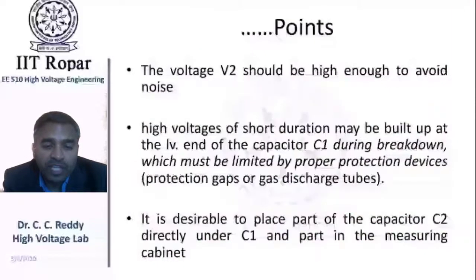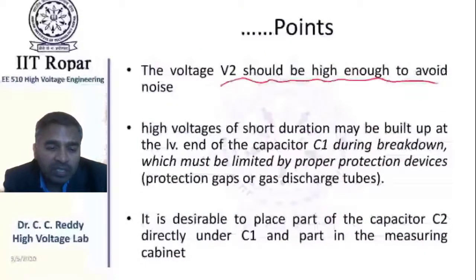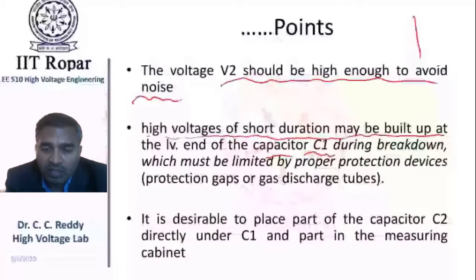And the voltage V2 should be high enough to avoid noise, because if V2 is small, then it is prone to noises due to the high voltage existing there, which may introduce noise on the cable also. So that signal on V2 should be high enough. And when breakdown occurs, a high voltage of short duration may be built up at the LV end of the capacitor C1. This is the HV end and this is the ground end of the capacitor. The LV end of C1 is connected to C2.